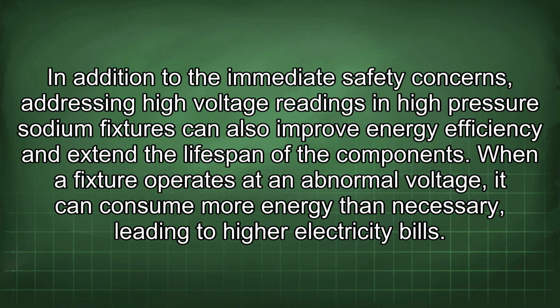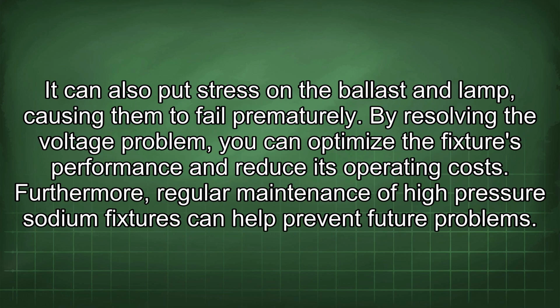In addition to the immediate safety concerns, addressing high voltage readings in high-pressure sodium fixtures can also improve energy efficiency and extend the lifespan of the components. When a fixture operates at an abnormal voltage, it can consume more energy than necessary, leading to higher electricity bills. It can also put stress on the ballast and lamp, causing them to fail prematurely. By resolving the voltage problem, you can optimize the fixture's performance and reduce its operating costs.